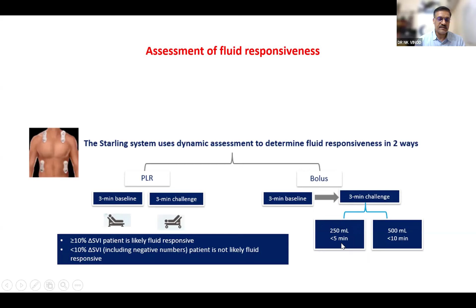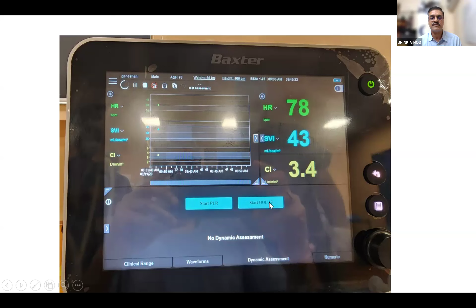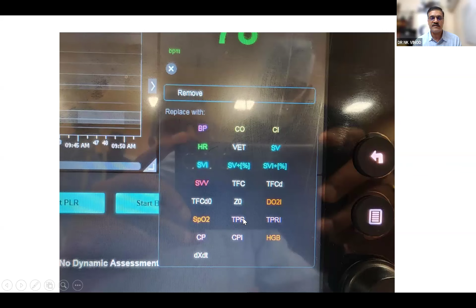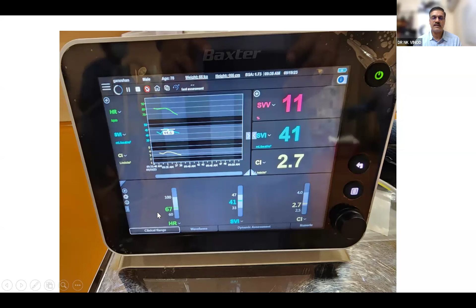So this is how the monitor looks like. You have the basic parameters and you also have the buttons where you can start the passive leg raise test or start the bolus test. The other parameters which can be measured by this monitor are the cardiac output, cardiac index, the thoracic fluid content and the peripheral resistance. And this is when we are measuring the stroke volume variation, stroke volume index, and you have the clinical ranges also, which are displayed in the monitor. And when we are giving the bolus, this is how the monitor guides us. It tells us when to end the bolus based on the timing which we are setting here.